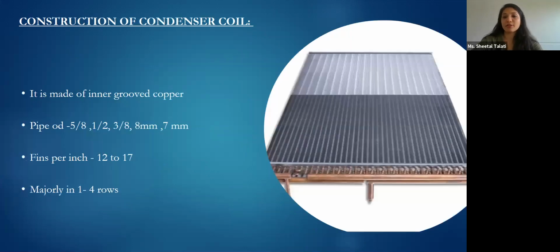Now, moving on to the construction of a condenser coil. A typical condenser coil is inner grooved pipe. The OD of the pipes are 5/8, 1/2, 3/8, 8 mm, and 7 mm. Usually, the fins per inch is 12 to 17 fins per inch. And majorly, these coils are compact in size, so you will find them ranging from 1 row to 4 rows.